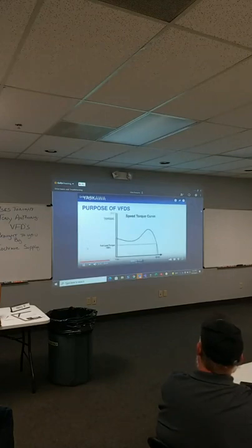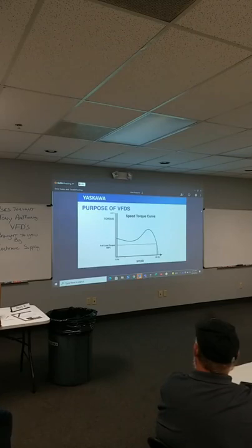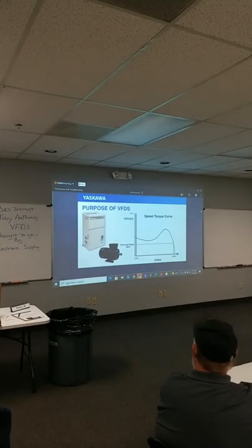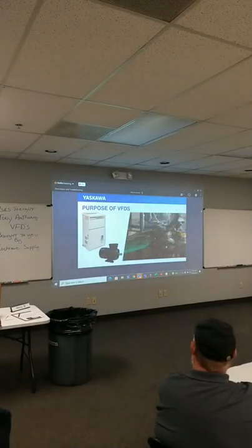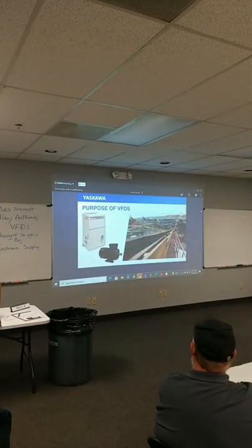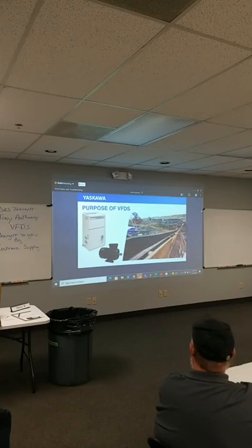Here are some of the major capabilities a drive provides. If you viewed the Motor Basics presentation, you saw this diagram showing an induction motor's relationship between speed and torque. By adding a drive to the system, we have the ability to alter the speed-torque curve. This lets us take advantage of the motor's characteristics at multiple speeds instead of being limited to only 60 hertz. VFDs allow us to match the speed of the motor-driven equipment to the load requirement. Operating a motor with a VFD provides full torque capability over a wide range of frequencies.